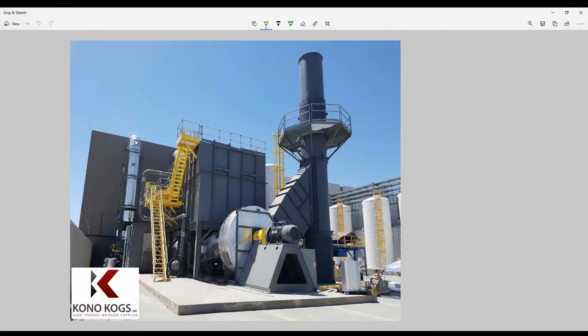Here we'll see the components that make up an RTO. This is the ductwork coming from the customer's process. VOC-laden air passes through the ductwork into a valve, into a ceramic media bed, up into the combustion chamber where the VOC destruction happens, past a burner, and then down through another bed into this valve, then into this fan, and then out clean to atmosphere. This valve will switch periodically and the airflow will change direction and go up through this bed, across the burner, across the combustion chamber, down into this bed.